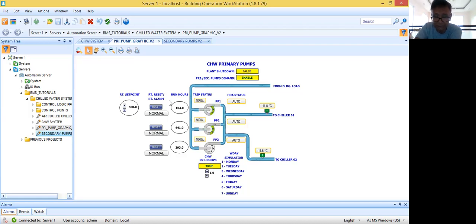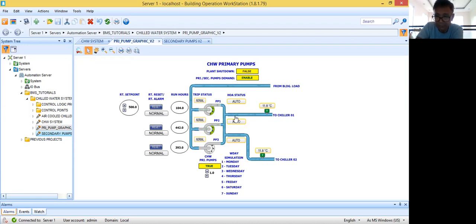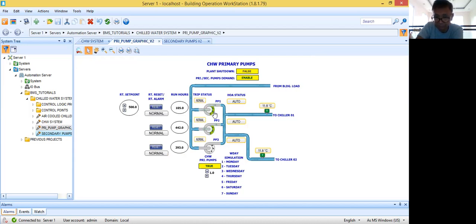As per my experience, I always show the run hours, because this is important for maintenance people. This pump is not maintenance-free equipment — it needs a maintenance schedule. The chief engineer or maintenance engineer handling this project will need a preventive maintenance schedule for the mechanical equipment. These run hours will help schedule maintenance, such as lubricating the pump bearings and doing adjustments. Let's say the pump runs at around 500 hours — my setpoint here is 500 hours.